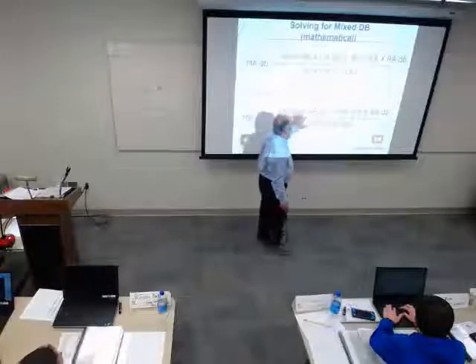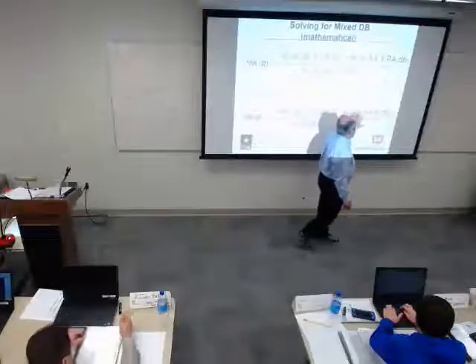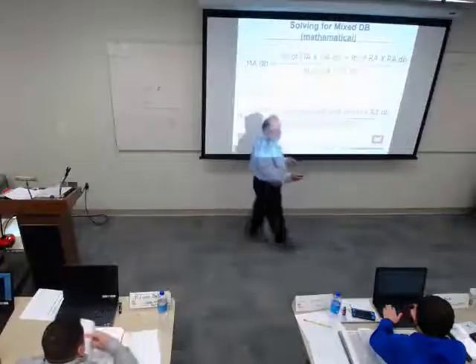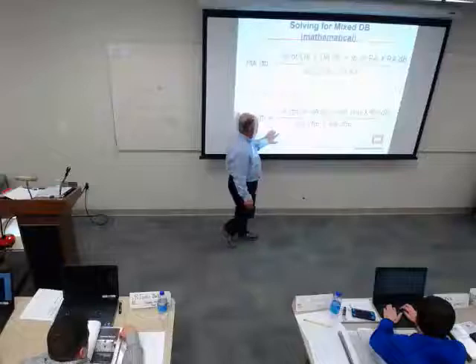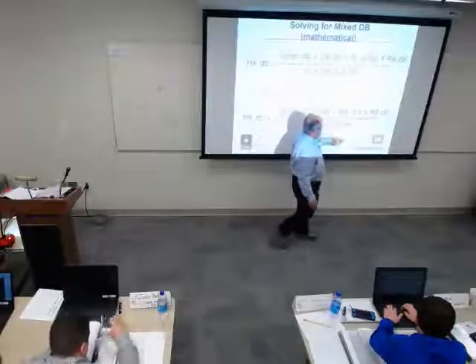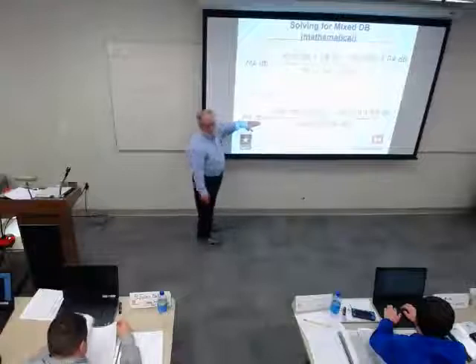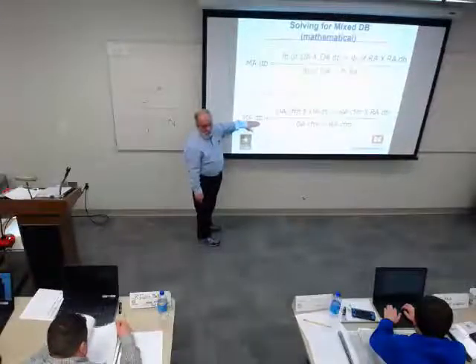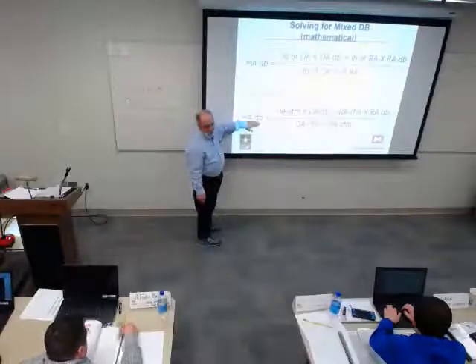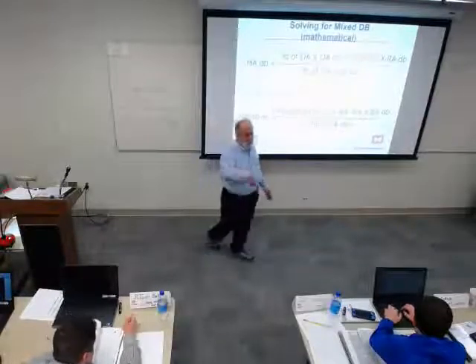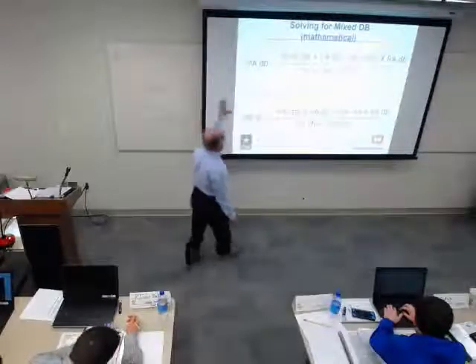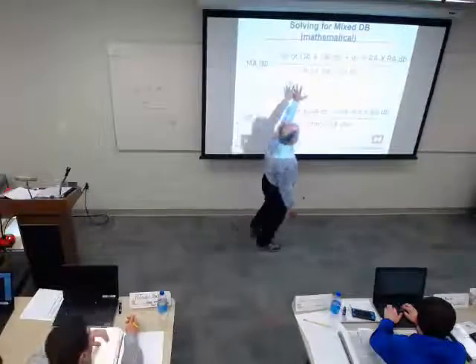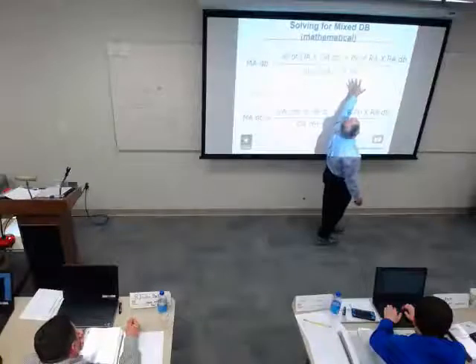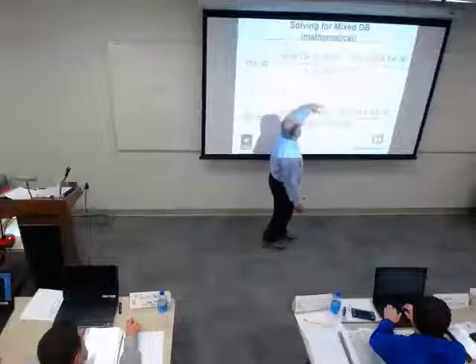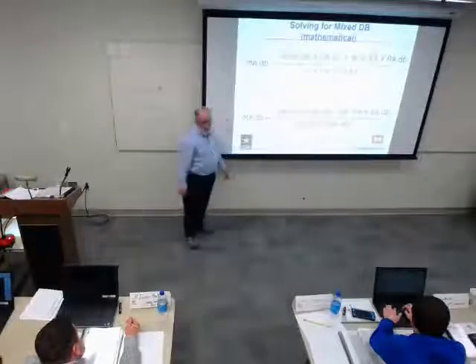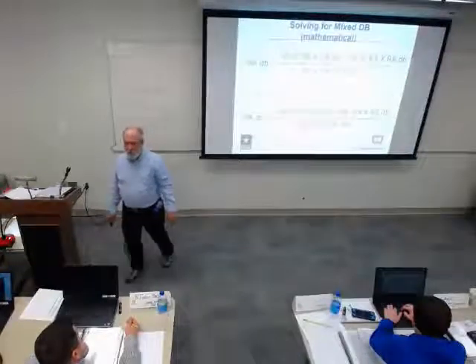We have the outside air CFM times the outside air dry bulb, plus the return air CFM times the return air dry bulb. Dry bulb is dry bulb temperature. And then we divide that by the outside CFM plus the return air CFM, and that gives us the mixed air dry bulb temperature. That also works for wet bulb and for dew points. And when we look at our psychrometric charts, you'll see why that is. That same thing works. We can do it on mass, or we use the pounds of outside air times its temperature, plus the pounds of return air times its temperature, divided by the total pounds. And again, we have the mixed air, which is the weighted average of those two.